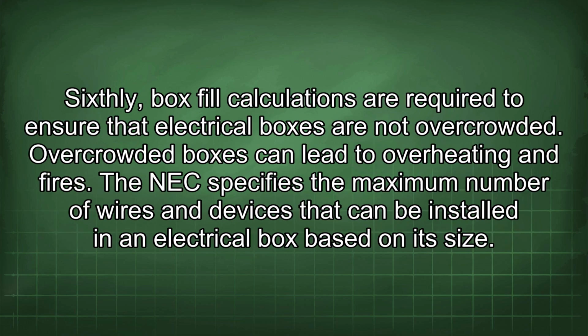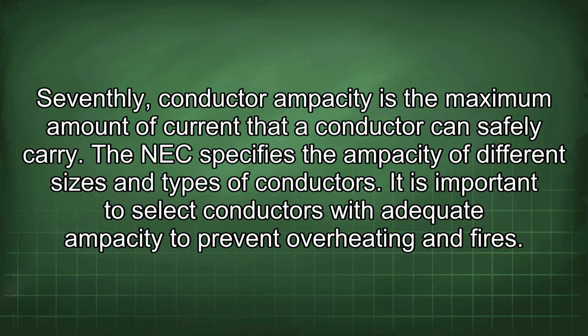Sixthly, box fill calculations are required to ensure that electrical boxes are not overcrowded. Overcrowded boxes can lead to overheating and fires. The NEC specifies the maximum number of wires and devices that can be installed in an electrical box based on its size. Seventhly, conductor ampacity is the maximum amount of current that a conductor can safely carry.